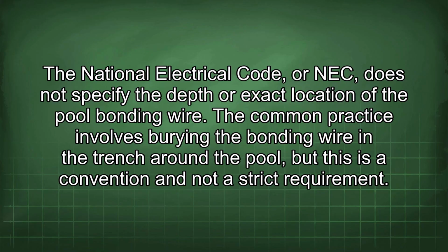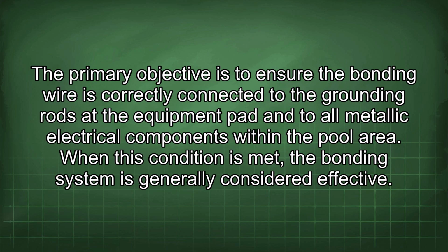The National Electrical Code, or NEC, does not specify the depth or exact location of the pool bonding wire. The common practice involves burying the bonding wire in the trench around the pool, but this is a convention and not a strict requirement. The primary objective is to ensure the bonding wire is correctly connected to the grounding rods at the equipment pad and to all metallic electrical components within the pool area. When this condition is met, the bonding system is generally considered effective.